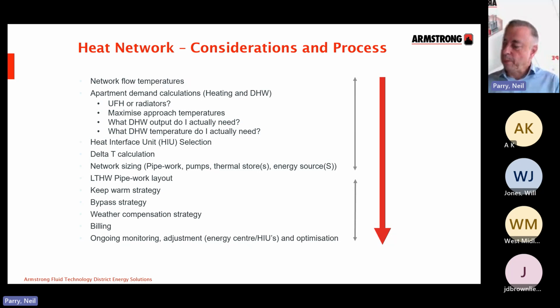Because if you think about every apartment with safety added in and you multiply that back down the network, the result at the energy centre can be significant oversizing. So what do I actually need? And what domestic hot water temperature do I actually need? Again, we talked about that earlier.